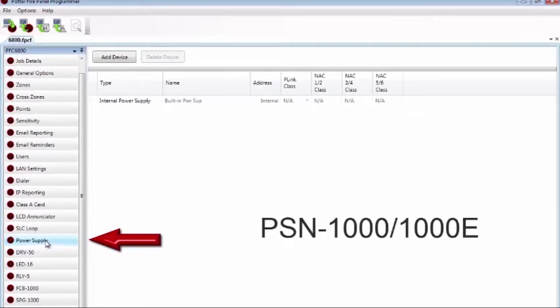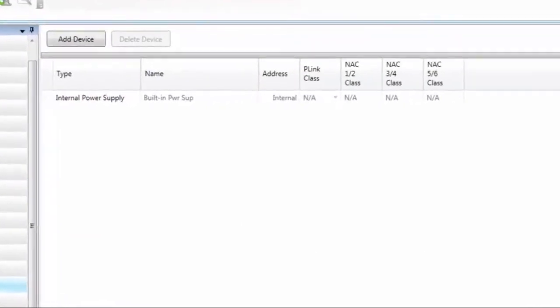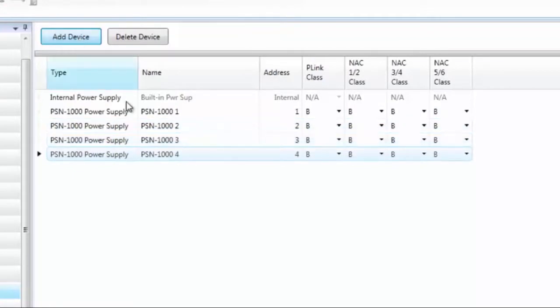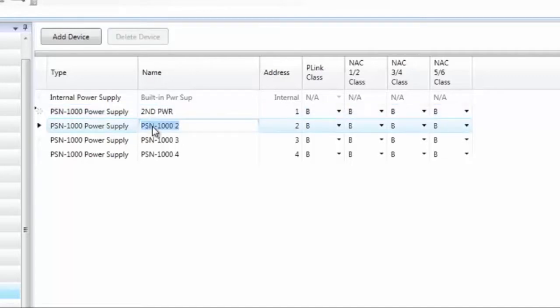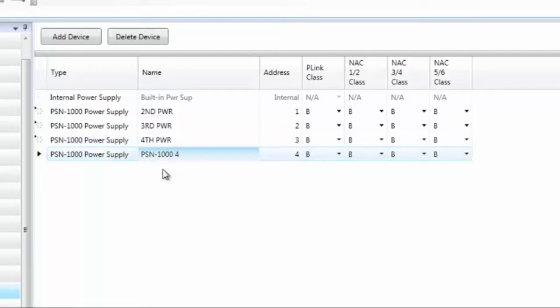Moving to the power supply — this deals with the PSN-1000, the smart power supplies connected via P-Link to the Fire Alarm Control Panel. You can have up to 31 of these on any of our systems. Click Add Device to add PSN-1000s. It is suggested to name these so that you can easily identify which device you're working with when you get to the Points list. We are simply adding the P-Link device itself here — when we get to Points, we'll configure all the points on the PSN-1000.